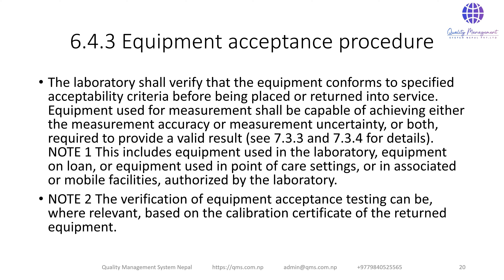6.4.3 Equipment Acceptance Procedure: The laboratory shall verify that equipment conforms to specified acceptance criteria before being placed or returned into service. Equipment used for measurement shall be capable of achieving the measurement accuracy or measurement uncertainty required to provide a valid result. This includes equipment on loan, equipment in point-of-care settings, or equipment in associated or mobile facilities authorized by the laboratory. Verification of equipment acceptance testing can, where relevant, be based on the calibration certificate of the returned equipment.